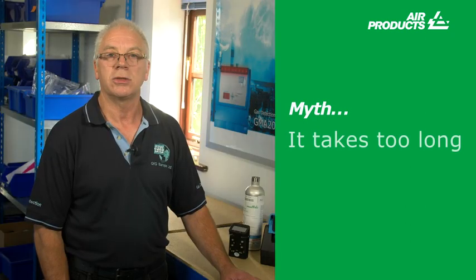The H2S exposure myth. It is dangerous to use a cylinder that contains 25 ppm of H2S. Using a 34-litre cylinder in a 1,000 cubic metre room, if the entire cylinder was emptied, the concentration in the room would only be 0.03 ppm. There is no danger. It takes too long. On average, a bump test takes no longer than 20 seconds.